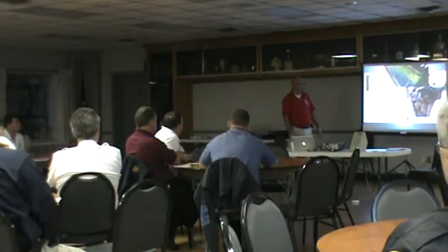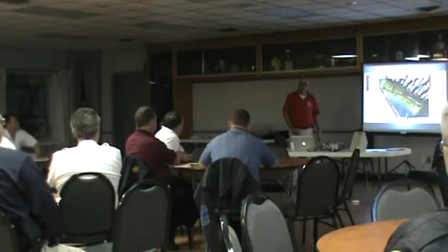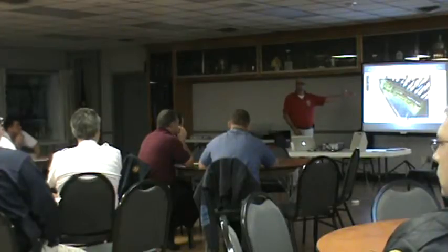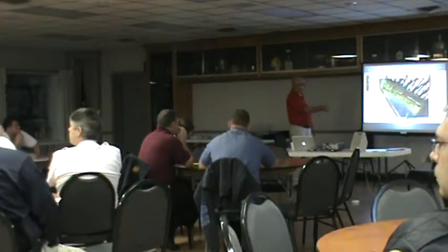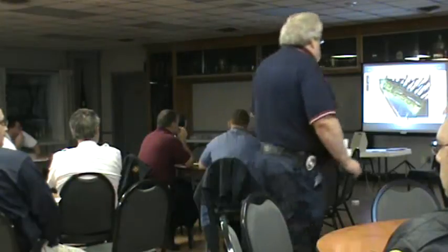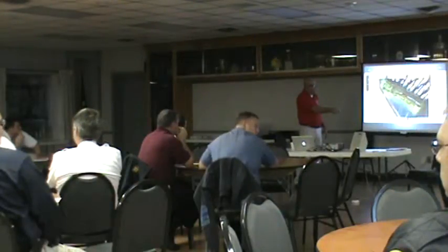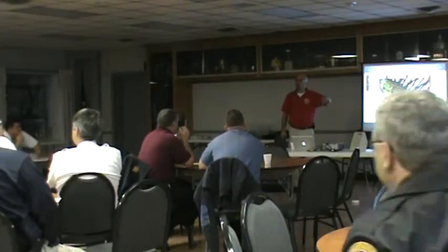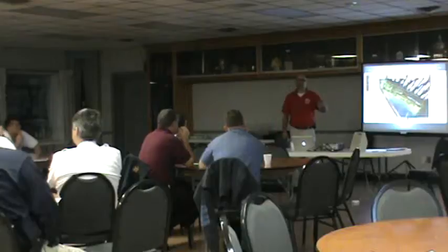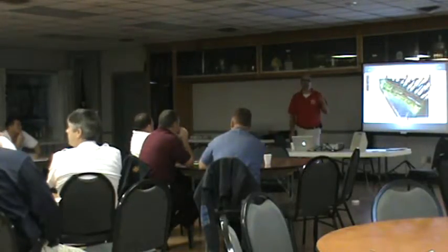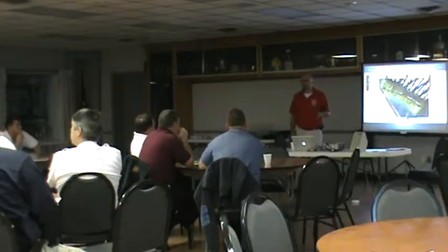Okay? So our job now is to basically show you the difference between original hardware and blatant repairs. See the square head bolt there? Is this what you need to see in order to say that it's bad? Or can you now look at a square head bolt, which is how old? Does anybody use square bolts today? So anything that still has a square bolt in it is how old? 50 to 75.